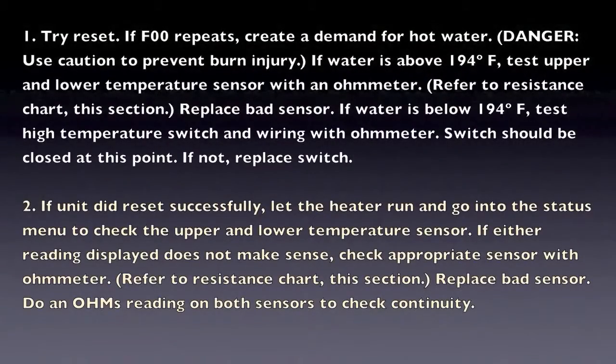If the switch is open, you will have to verify the temperature by either measuring the temperature coming out of a tap or measuring the resistance of the upper sensor.